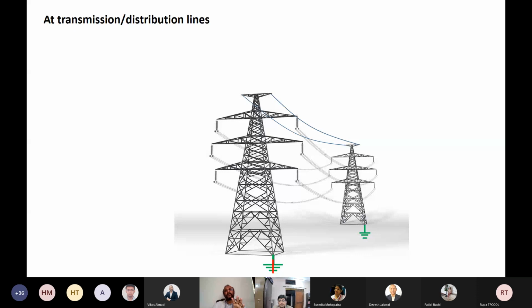But it's very important to understand that you have to look at the phenomena rather than looking at the solution when it comes to addressing the lightning related issues of the power lines. Now consider that a lightning gets attached to a tower or the shielding wire, and what happens is that a part of the lightning current will flow into the tower closest to the lightning strike, but another part will go to the other towers as well. Here, just for clarity, I have taken only 2 towers, but it may go into several towers.